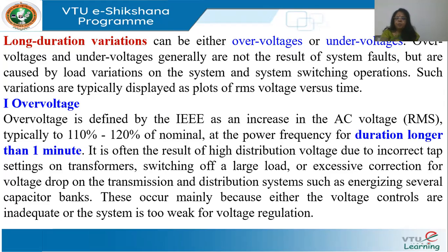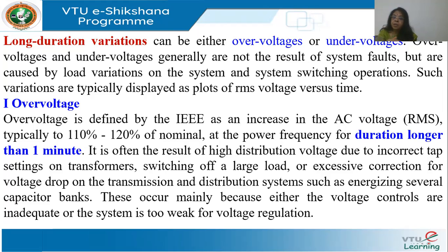As defined by IEEE, over voltage is an increase in the AC voltage RMS value, typically to 110 to 120 percent of nominal (1.1 to 1.2 per unit) at power frequency, for durations longer than one minute. Up to 110 percent of nominal is not considered over voltage — only above 110 percent qualifies.